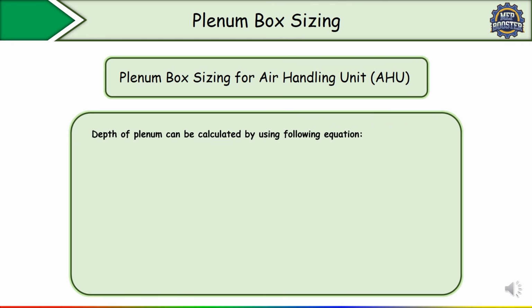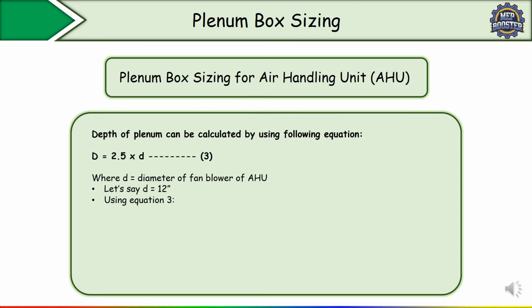As I told you, the depth of the plenum box can be calculated using the following equation. You have to multiply the blower diameter by this factor of 2.5. The blower diameter you will get from the manufacturer side. Here we are assuming the diameter of the fan blower of the AHU is 12 inch, correct? So when you substitute this 12-inch value in equation number 3, the depth of the plenum box is 2.5 feet. In this way we have to calculate the plenum box sizing for an air handling unit.